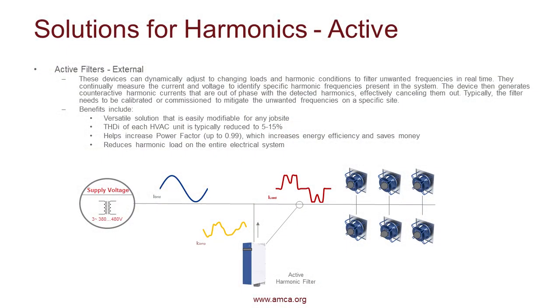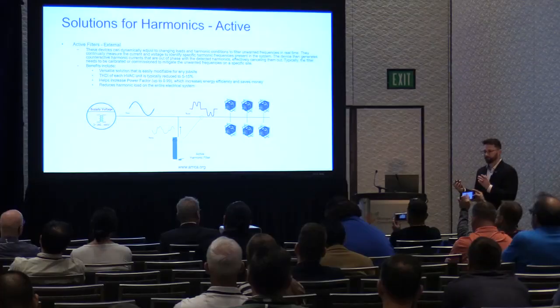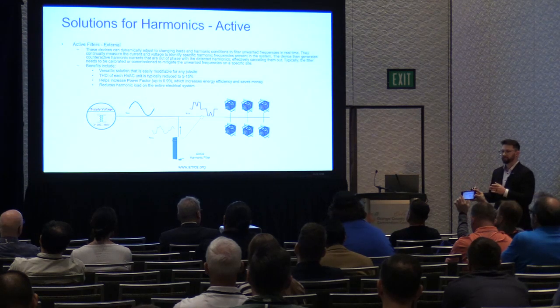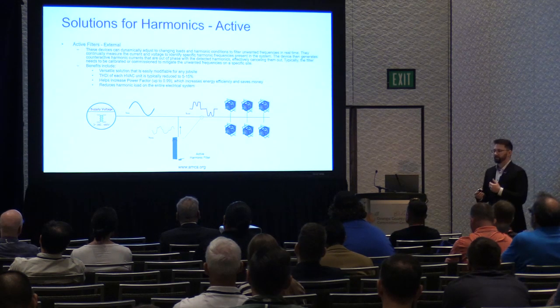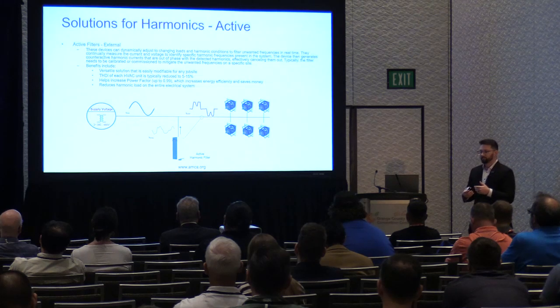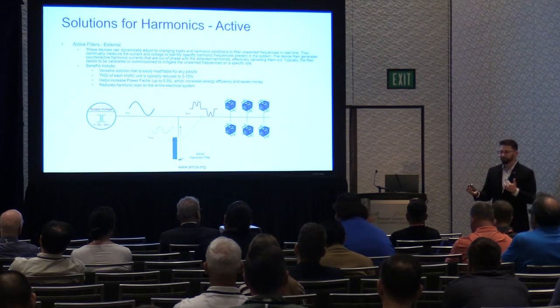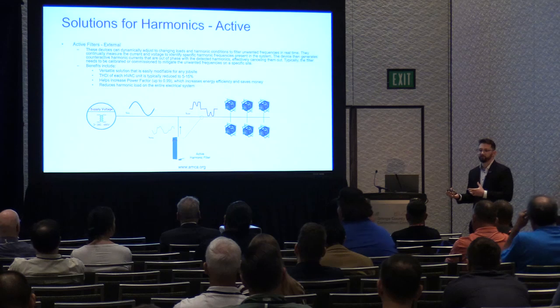So now we can talk about active filters. So active filters, what they're doing is they're using sensing technology where they're looking at your current, they're looking at your voltage, they're monitoring this, and then they're creating a sinusoidal wave, a counteractive wave to the harmonics that it's seeing.